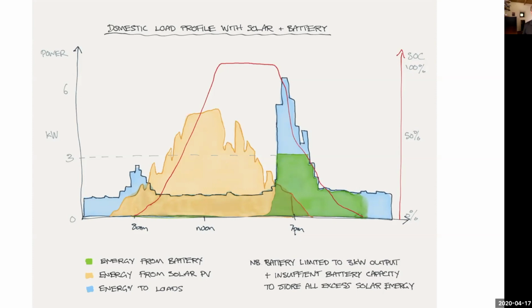But with lead acid, you're actually trying to charge the battery for a chemical reason, to reverse the damaging effects of sulfation. A lead acid battery needs to be fully charged to protect it from sulfation on a regular basis - ideally every day, but at least every few days. If you don't do that, and you've undersized your PV so the battery's bouncing along all winter because it's only going to get fully charged in summer, you would damage a lead acid battery. It's one of the most common reasons for failure - what's called partial state of charge cycling, not letting a lead acid battery fully charge.